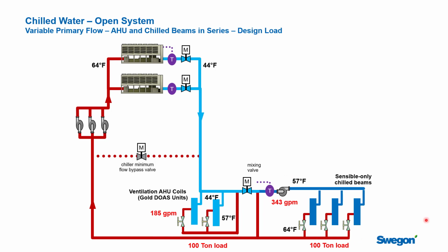Let's go look at what's going on inside the chilled beam loop. Now I have 100 tons of chilled beams out here, but I have a much smaller delta T across these. We're going to heat that water from 57 to 64 as we cool the space down. And you can back into that number and you're going to realize that this pump is pumping 343 GPM for this tonnage. And so you can see the flow rates instantly don't line up.